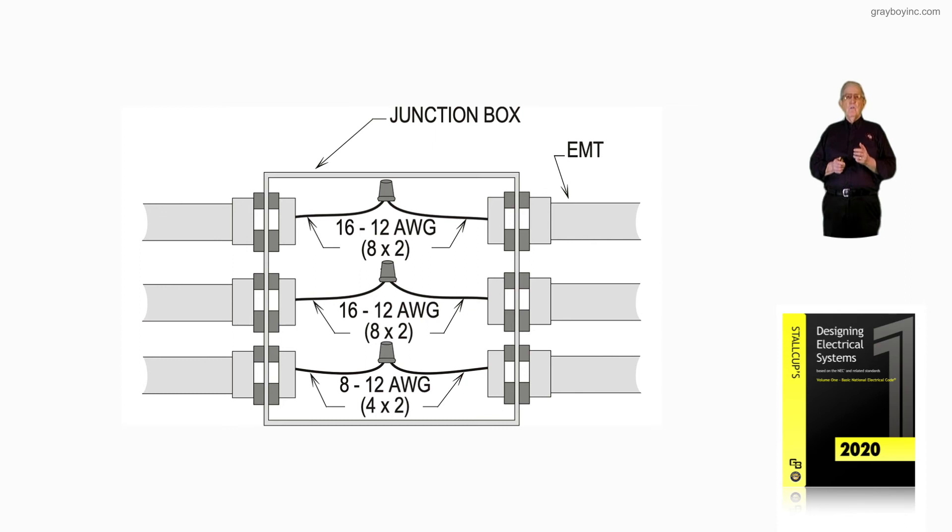The same below, we have 16 number 12, so two of them, one from each side coming in would be 16. And then we would have eight number 12, so that would be 2 times 4 in this case, and we would come up with the 8 that you see there. So with this knowledge, by reviewing what's in the box, we can now go to figure 12-15B and do the calculation inside the junction box.